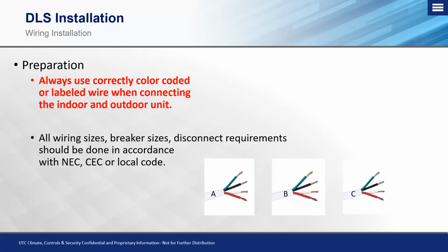So again, we need to make sure that all wiring sizes, breaker sizes, and disconnect requirements are done in accordance with NEC, CEC, and most importantly, your local code for electric wiring. Okay, and again, always make sure that you use color-coded labels for your power and communication so that you do not get those signal wires and power wires crossed.